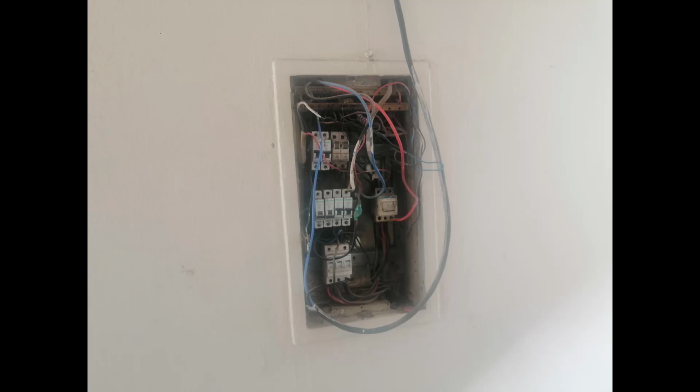some level of rewiring of that building that supplies the other areas where we were discovering the fault. While doing that, we replaced circuit breakers, because the circuit breakers that were there were actually faulty. You can see an image of it on your screen. We replaced the circuit breaker, the main switch, and some other breakers. When we did that, we made a proper connection, because initially most of the cables connected to that distribution board were just looped.